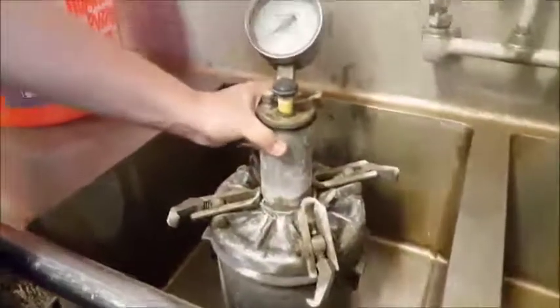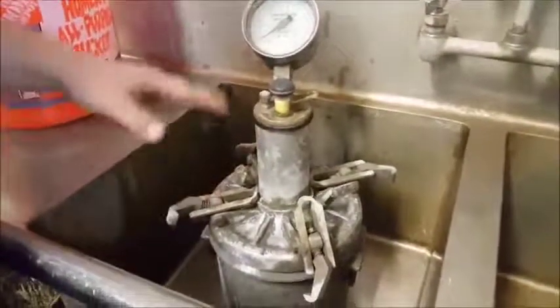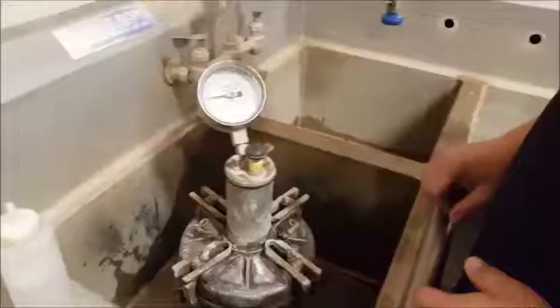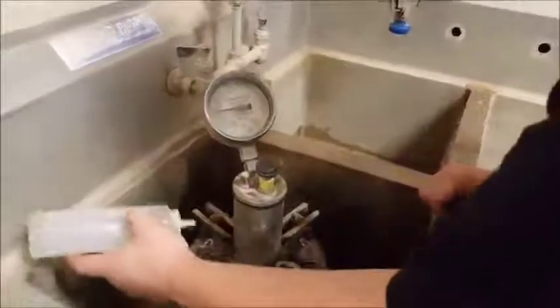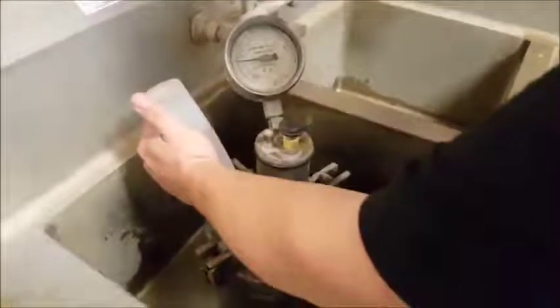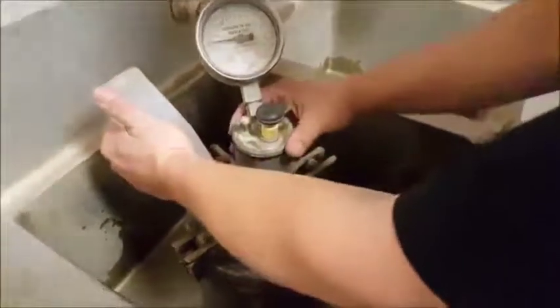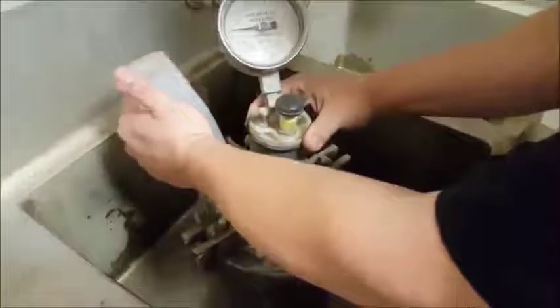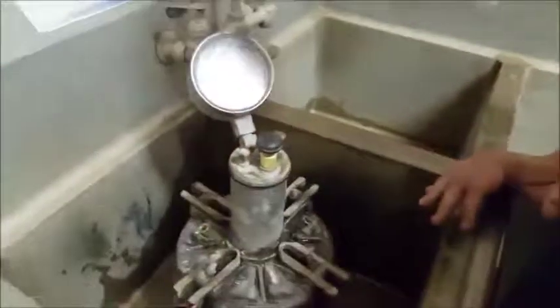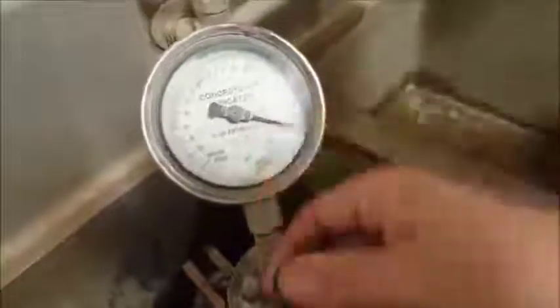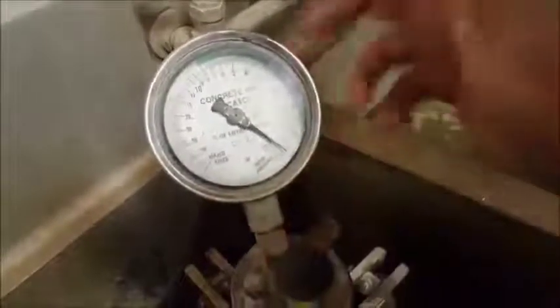And at this point, we're going to go ahead and clamp this down and fill it up. So we're going to make sure we got this filled up. We want to fill this from the same side that the tube was in. So that's why it's important to remember which side the tube's in. Next, we're going to pump this up to the initial pressure. And on this gauge, the initial pressure is 2, marked at 2.